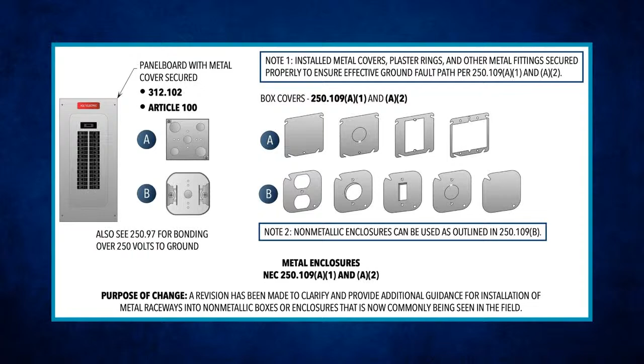Then it says if you install any type of metal covers, extension rings, plaster rings, or any metal fittings, they're required to be attached to the metal enclosure. That also ensures your effective ground fault current path, or they have to be connected with bonding jumpers or equipment grounding conductors, or both. If you're dealing with anything over 250 volts to ground, they have an informational note telling you to go see 250.97.